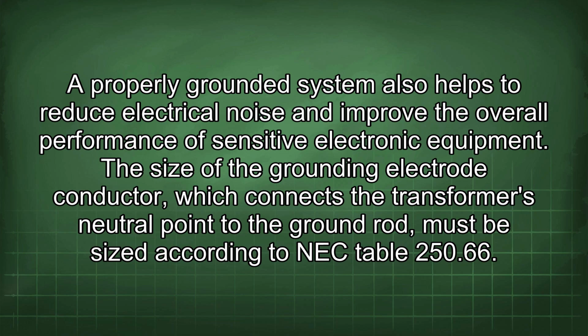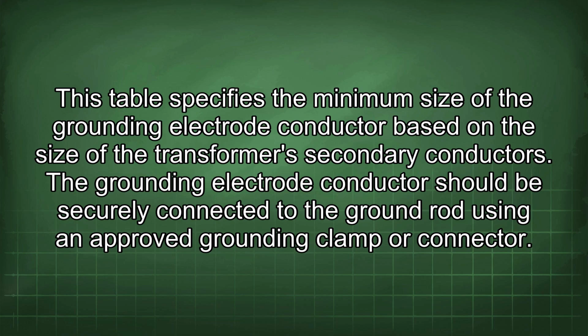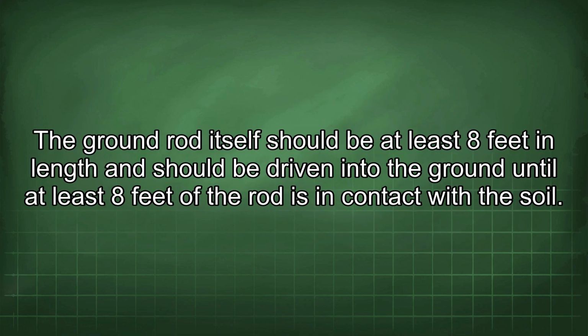The size of the grounding electrode conductor, which connects the transformer's neutral point to the ground rod, must be sized according to NEC Table 250.66. This table specifies the minimum size of the grounding electrode conductor based on the size of the transformer's secondary conductors. The grounding electrode conductor should be securely connected to the ground rod using an approved grounding clamp or connector. The ground rod itself should be at least 8 feet in length and should be driven into the ground until at least 8 feet of the rod is in contact with the soil.